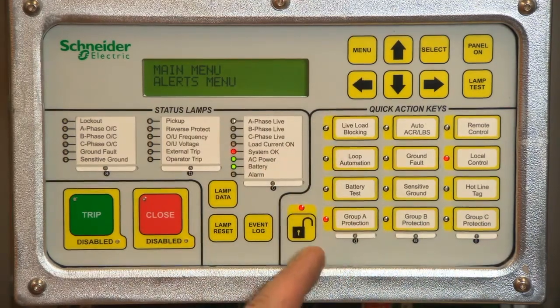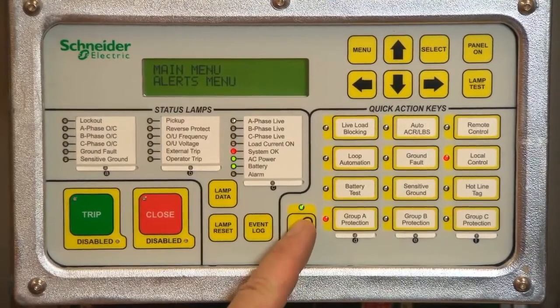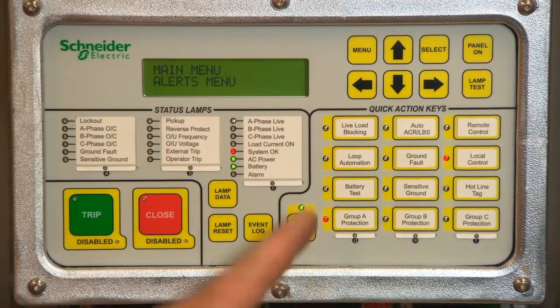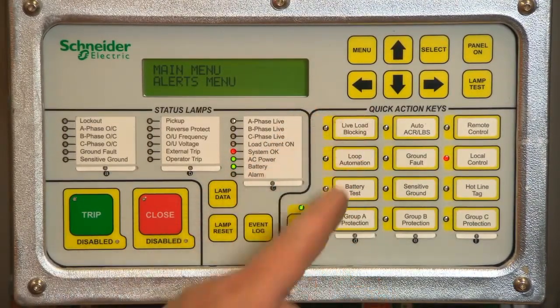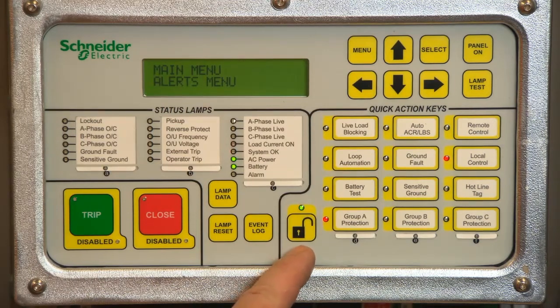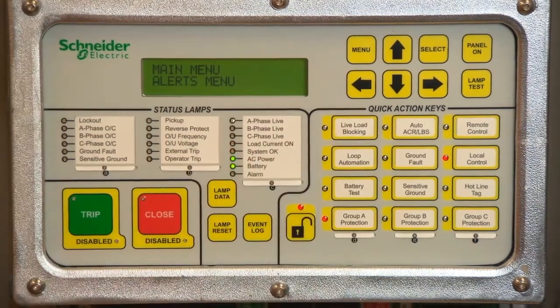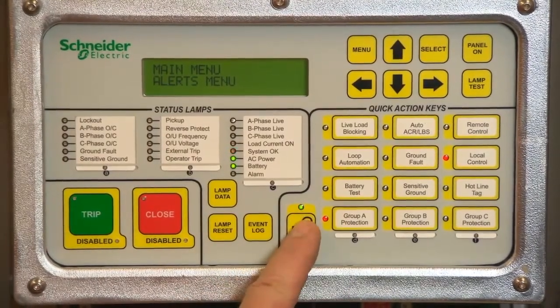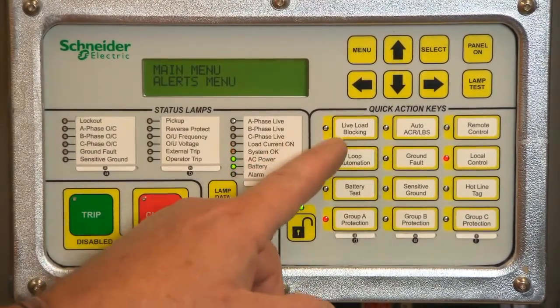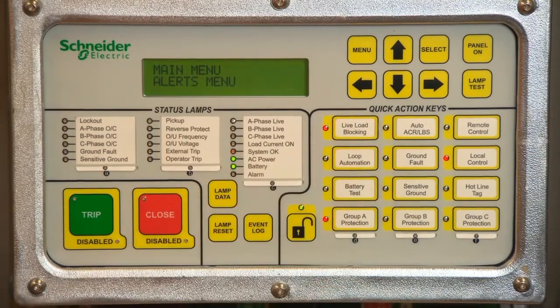To activate live load blocking, first press the lock button, followed by the live load blocking button. This will detect any voltages on the load side of the recloser. If voltage is present, it would not be allowed to be closed. This is typically not used. In order to close the recloser, you must turn off the live load block feature.